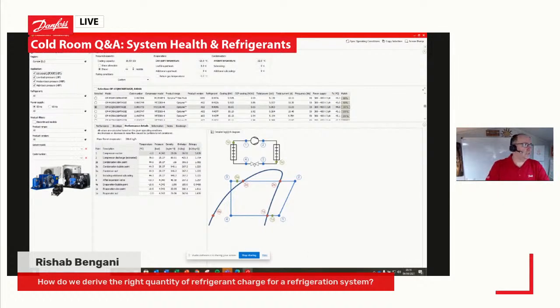So this is a condensing unit selection. You can also do it on the compressor selection as well. And if you put in your system information, your refrigerant information, etc., I'll just choose 449, for example. So we've got our cooling capacity, our evaporating temperature, ambient temperature, things like that.